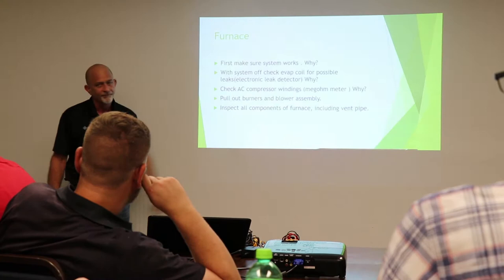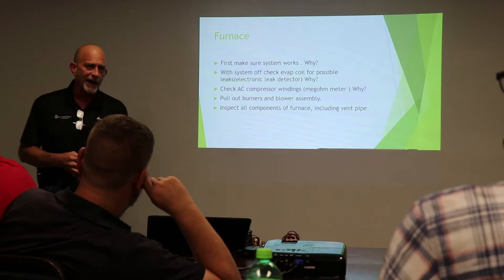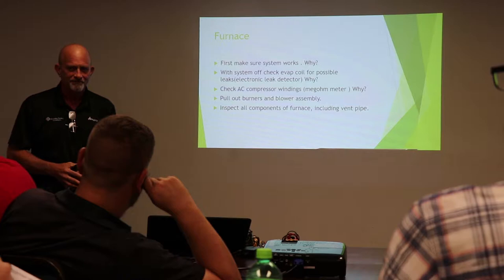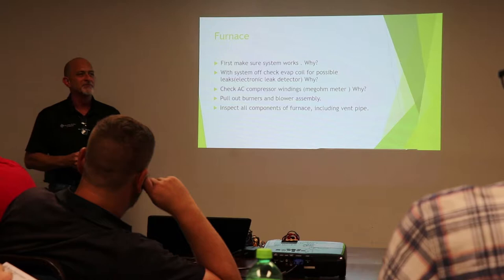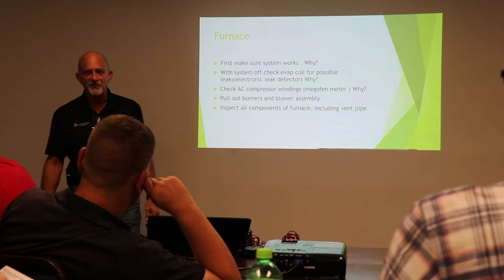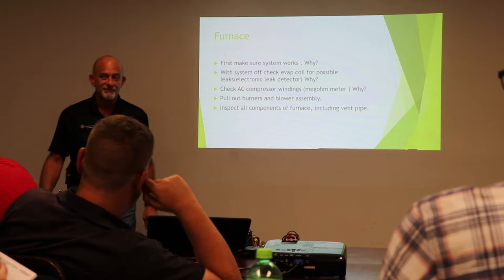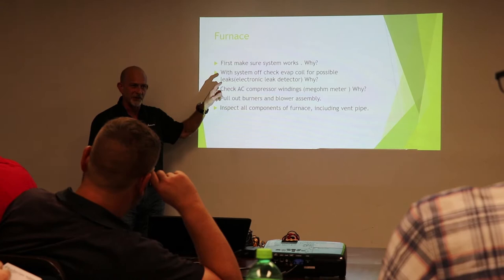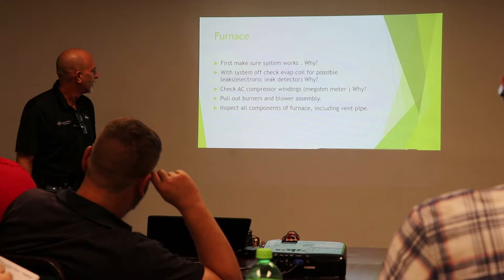Make sure the system works before we even start, before we start taking it apart. Why would we do that? So that if it doesn't work when we're down there checking it, and they say, well, it worked, why are you got in here? Exactly right. Homeowners misconstrue the difference between a service call and a cleaning check. Especially if you're advertising a $39 cleaning check to get you in the door, where you may charge $96 for a service call. I want a cleaning check for $39.95, knowing that their system doesn't work. So that one's cover your own butt. It works before you touched it. Now, shut the system back off, now we go downstairs.